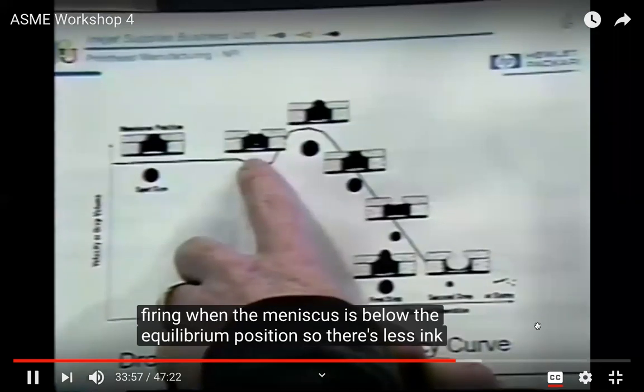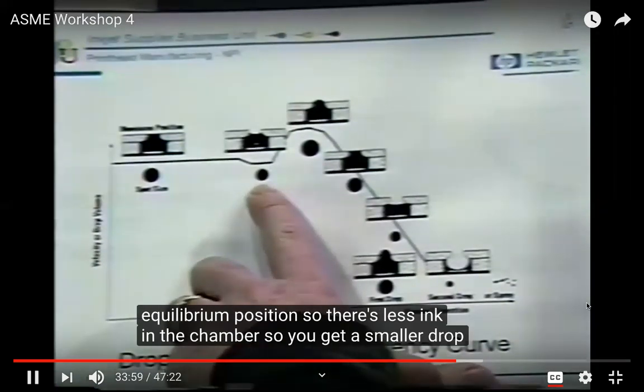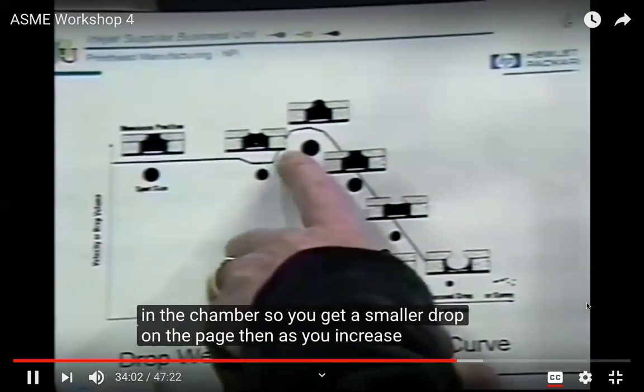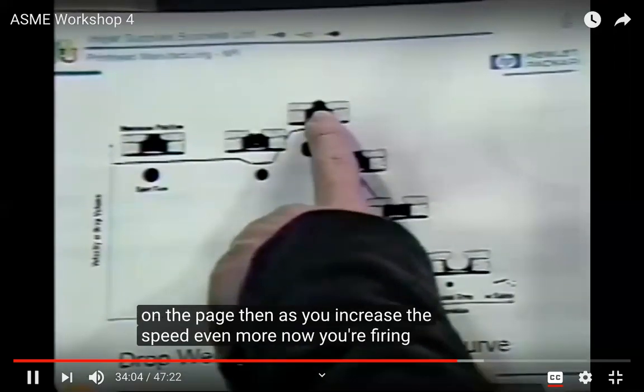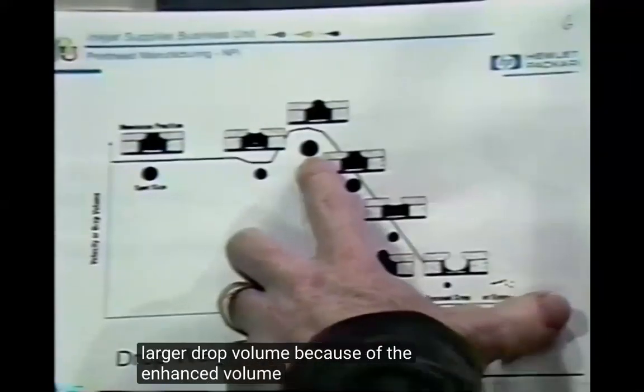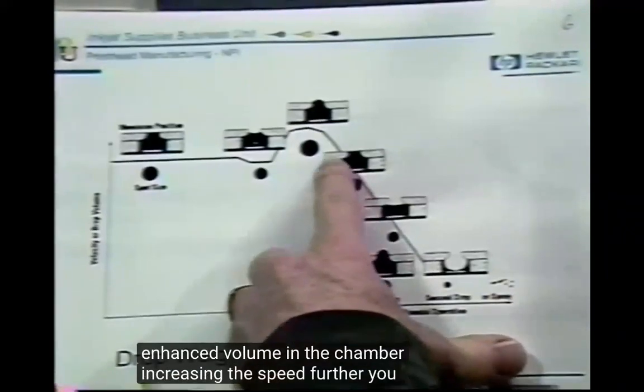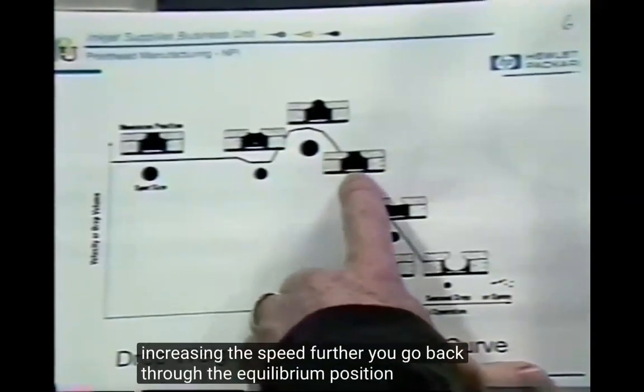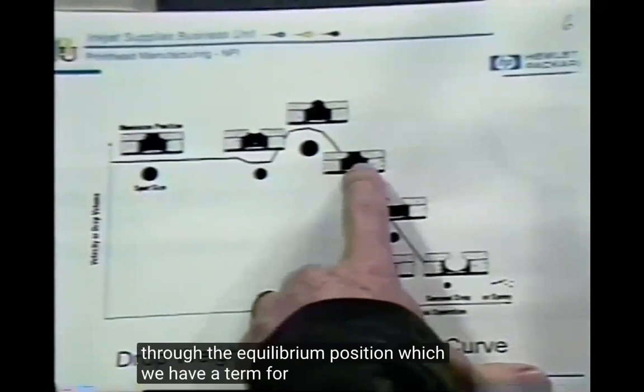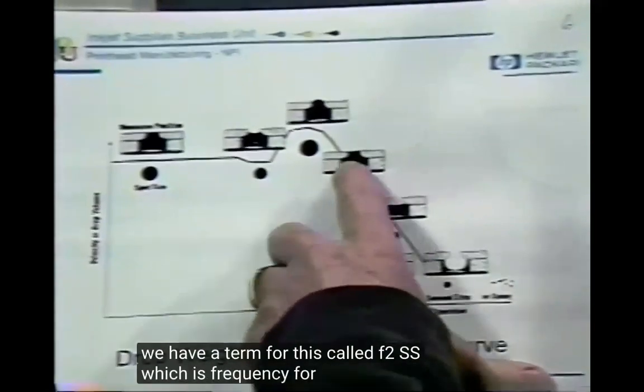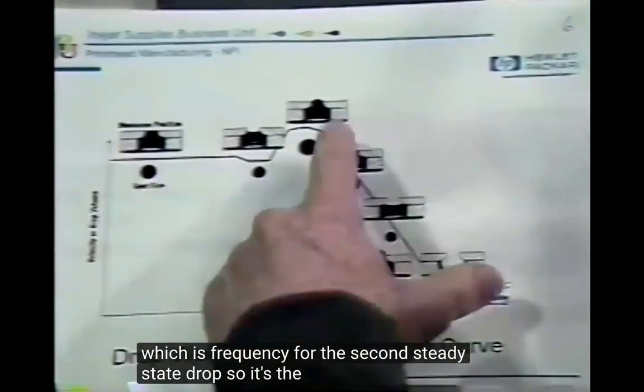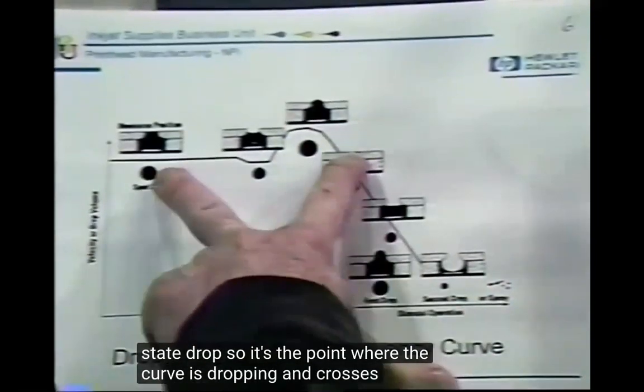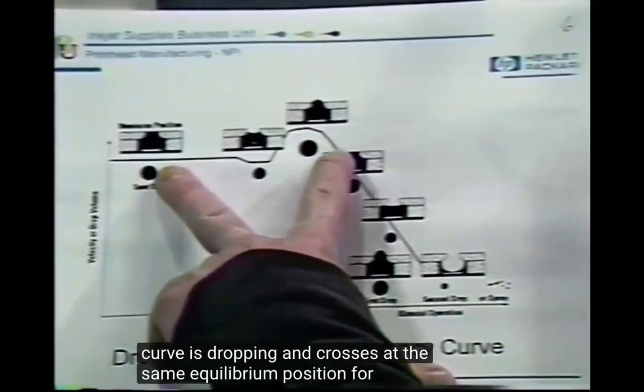Then as you increase the speed even more, now you're firing on what we call the bulge, where the meniscus bulges out from the chamber, and you're getting a larger drop volume because of the enhanced volume in the chamber. Increasing the speed further, you go back through the equilibrium position, which we have a term for called F2SS, which is frequency for the second steady state drop. So it's the point where the curve is dropping and crosses the same equilibrium position as for the low speed.